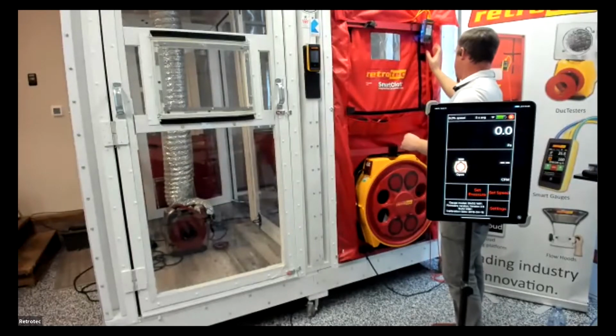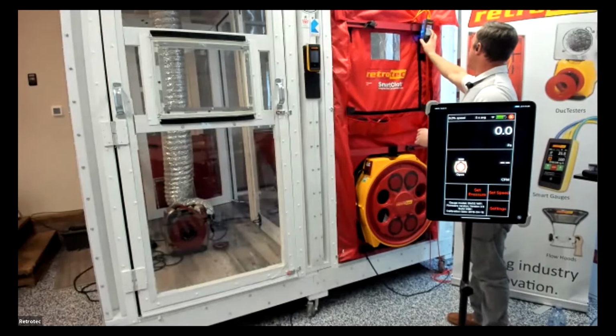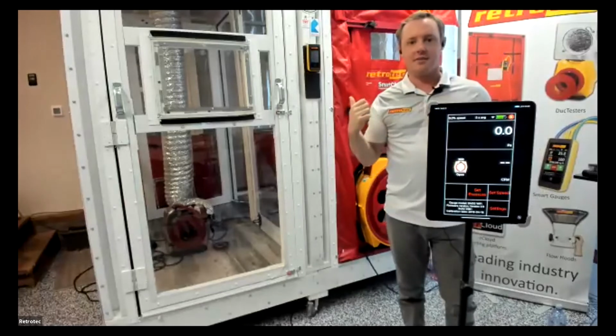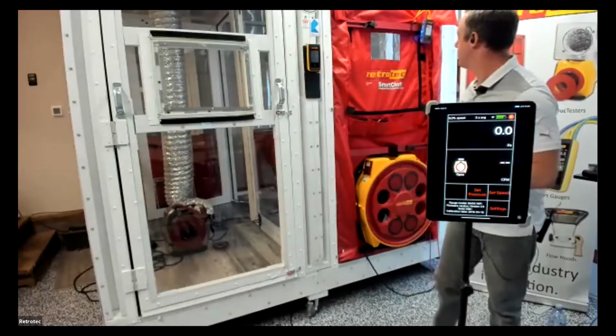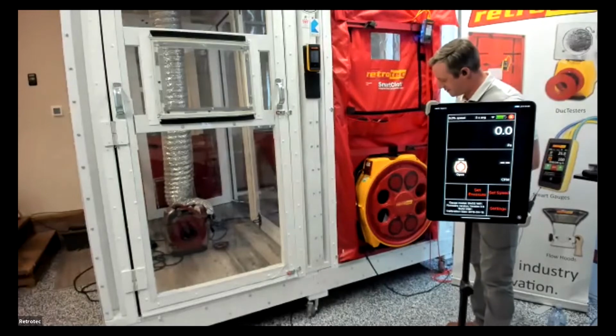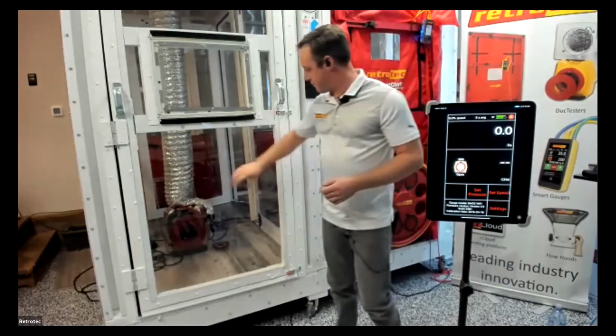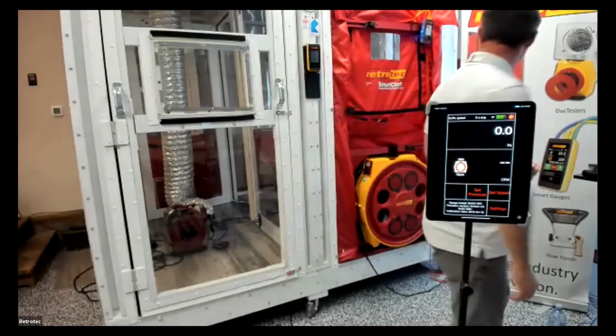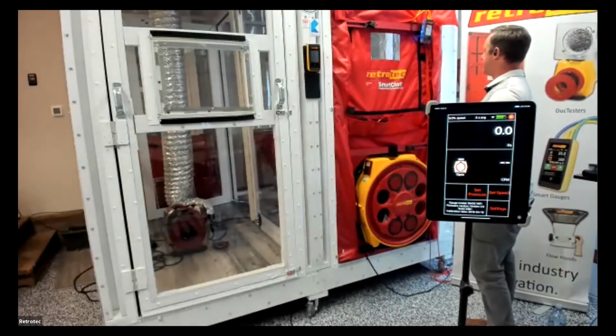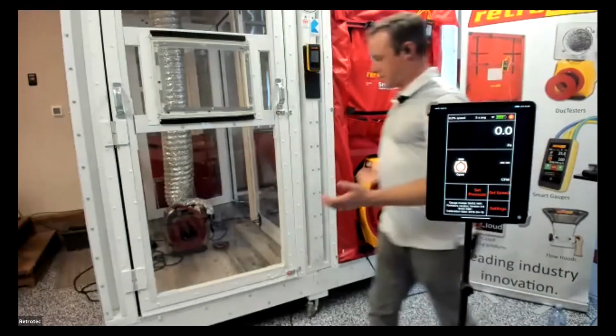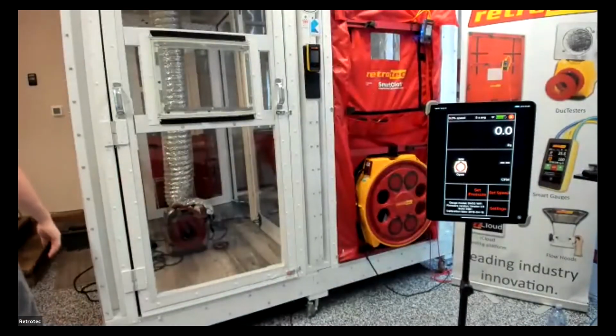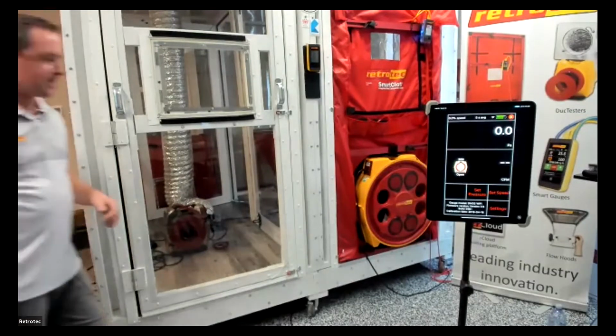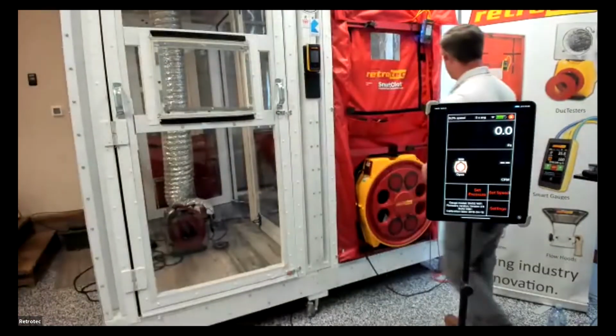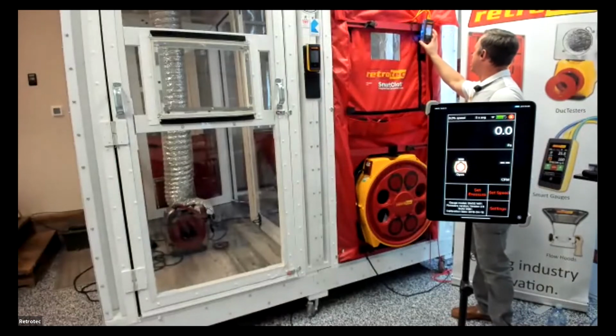So we'll go ahead and pop this on here. I don't care what the flow is. All I want to do is get the space to positive 25 in this case. And I'm pressurizing this time just so you guys can see the inlet sides of the fan in case I need to change the range or anything like that. So I make sure I've got my doors shut. Obviously, in this case, you can't leave a door or a window open or the blower door will not get the pressure. So we'll go ahead and seek 25 pascals.